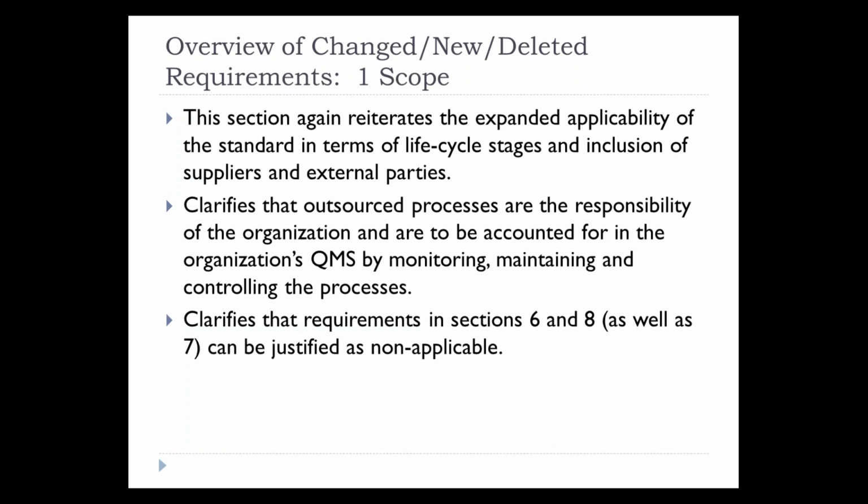Clarifies that requirements in Section 6 and 8 as well as 7 can be justified as non-applicable. So previously it was just Section 7, now this opens it up to Section 6 and 8. And again, that second bullet point is really important. Just because something is outsourced, the organization that's seeking certification to ISO 13485 is still responsible for those outsourced processes. You need to manage your supplier.